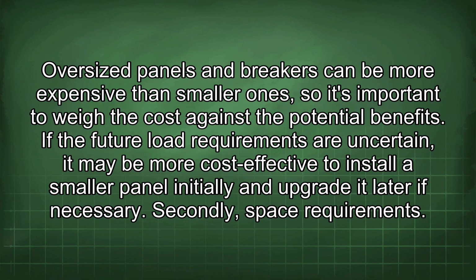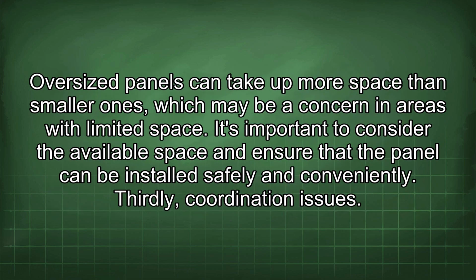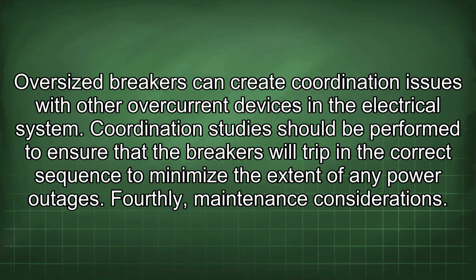Secondly, space requirements. Oversized panels can take up more space than smaller ones, which may be a concern in areas with limited space. It's important to consider the available space and ensure that the panel can be installed safely and conveniently. Thirdly, coordination issues. Oversized breakers can create coordination issues with other overcurrent devices in the electrical system.